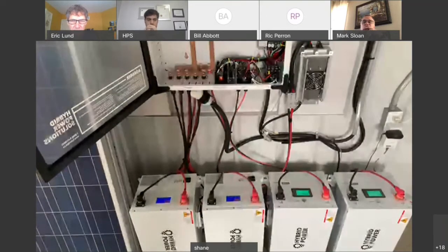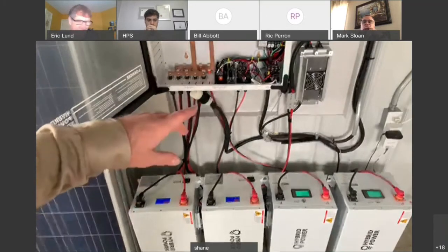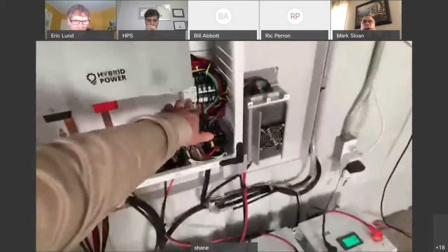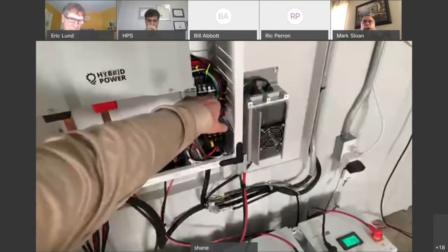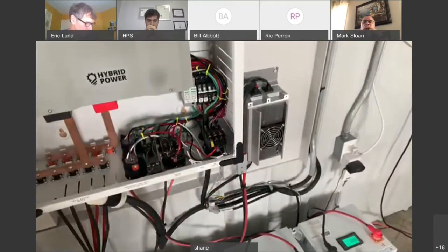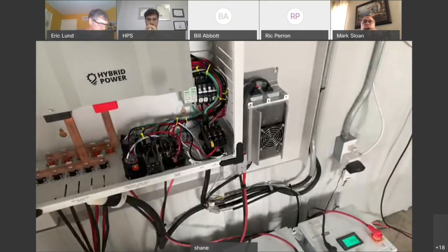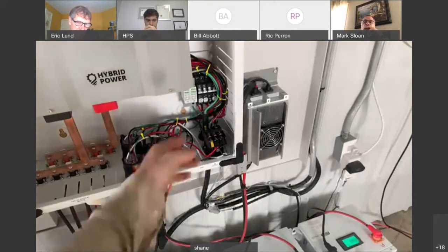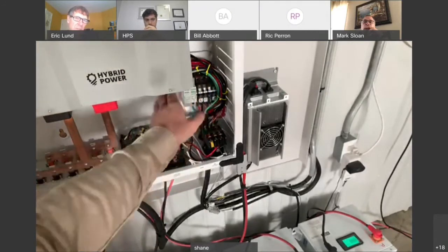We could talk a little bit about the PV side, and that's the same thing. We have our surge arresters and our 2 strings and our main output. So the way I like to size it is we have 30 amps per leg. So per string. So that means we could put 1500 watts or just over 1500 watts per 30 amp string. The way I do this is I put 4 panels on an array on 1 string. So let's say I have 4 380 watt bifacial panels coming in at 1500 watts when it hits the breaker. Now they're parallel on the top side of the 63 amp breaker, so now I have 3000 watts going into my PV.